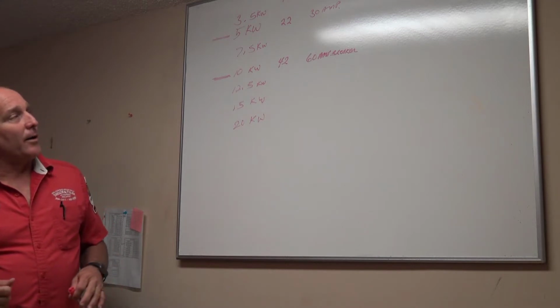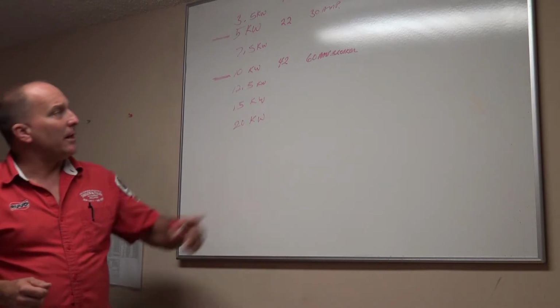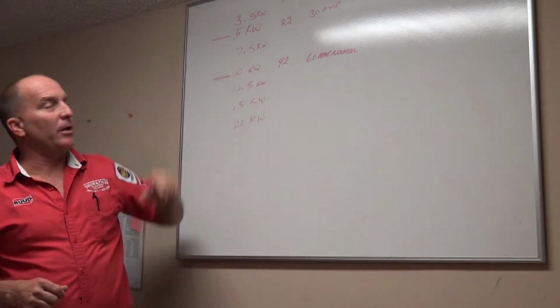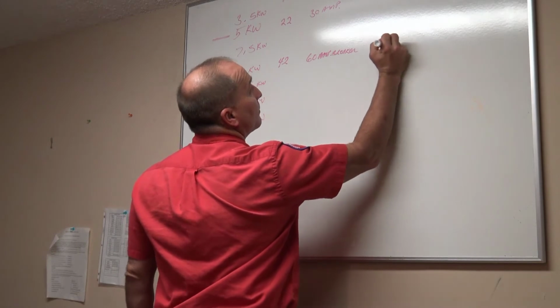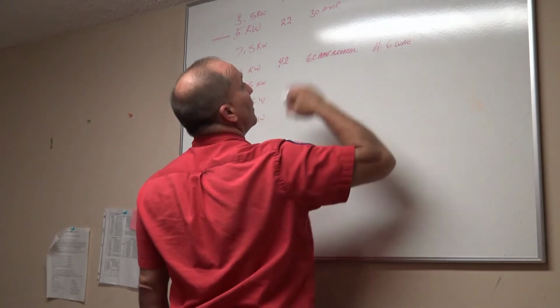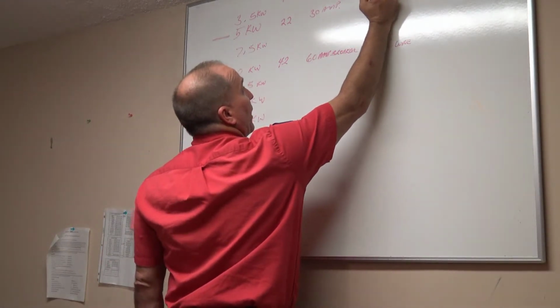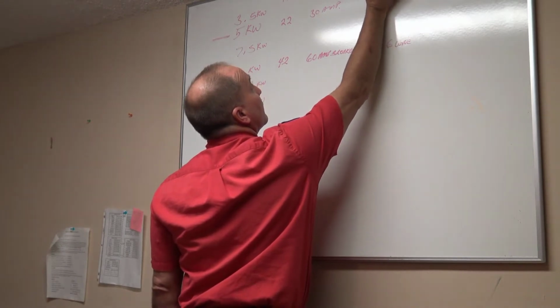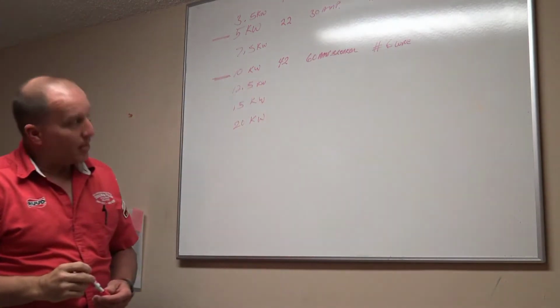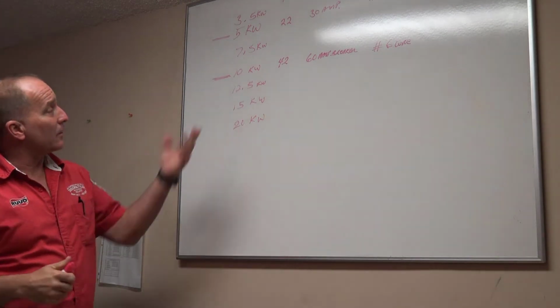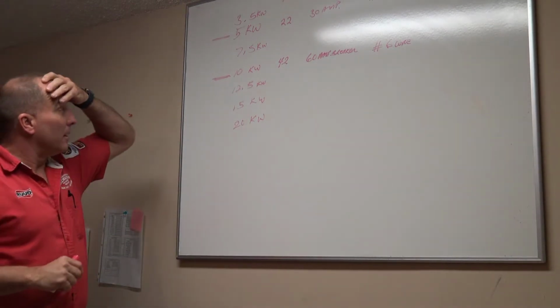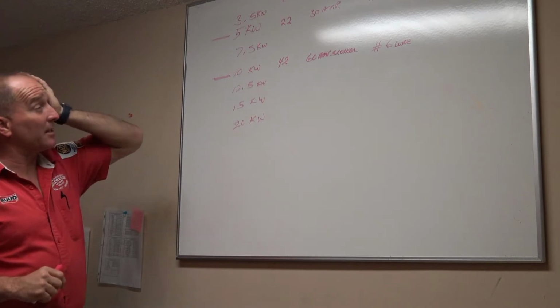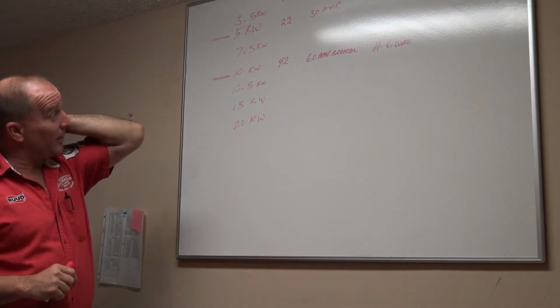What size wire would I run into a 60 amp breaker to hold 42 amps? It is going to be a number 6 wire. What size do I need for 30 amp? Number 10 wire. All right. What else do we need to know across the board here, guys? 10 kW, 42 amp, 60 amp breaker, number 6 wire. Anything else we need to know?